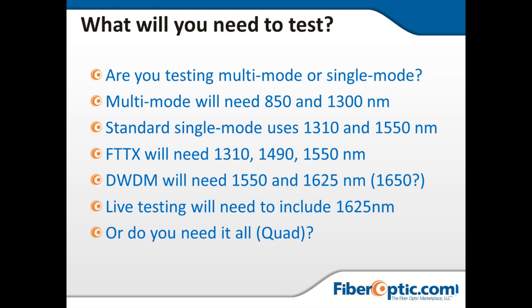That's why we recommend 850 and 1300 for multimode — I always recommend those two wavelengths. Standard single mode uses 1310 and 1550. But standard single mode starts to get a little more complicated every now and then, and we see certain circumstances where additional wavelengths have been added that may not have been standard 10 or 15 years ago.